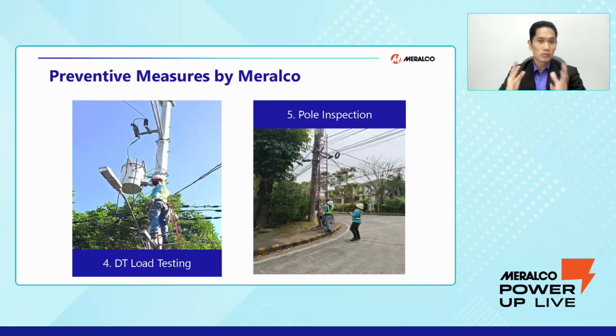And also distribution transformer load testing. Meralco has this program in order to check whether the distribution transformer serving our customers is still within the efficient loading, let's say from 40 up to 80% load of the transformer. So once it is found overloading, more than 100%, Meralco will have a program to correct this overloading of our transformers. It depends on whether our contracted capacity is within the contract, so Meralco will correct this without having our customers pay. But if our contracted capacity is exceeded, the customers will have to upgrade their contract in order for our facilities to upgrade as well.